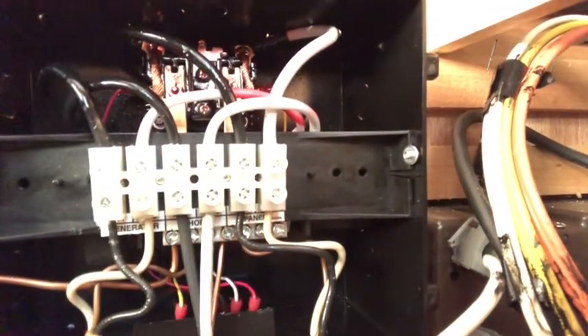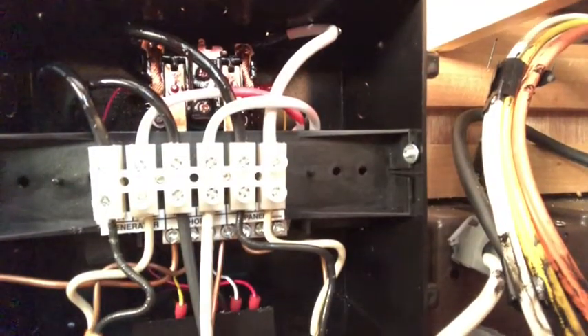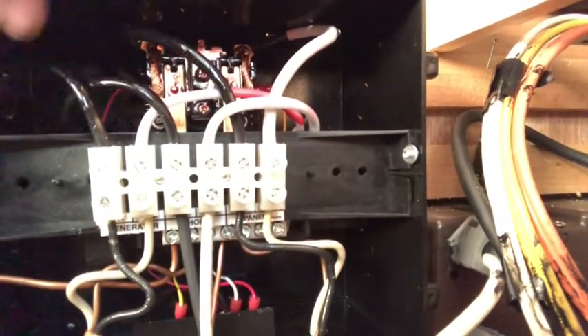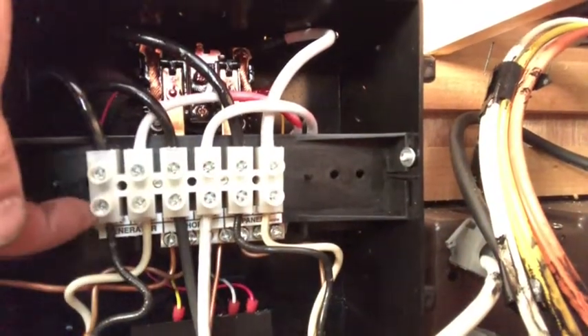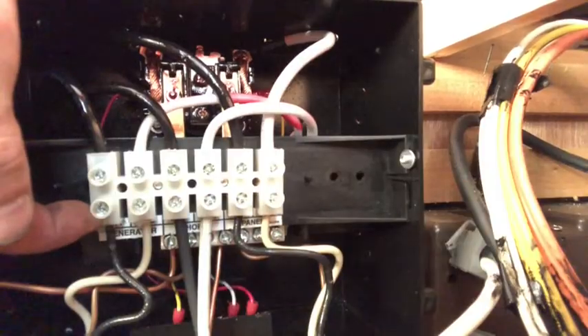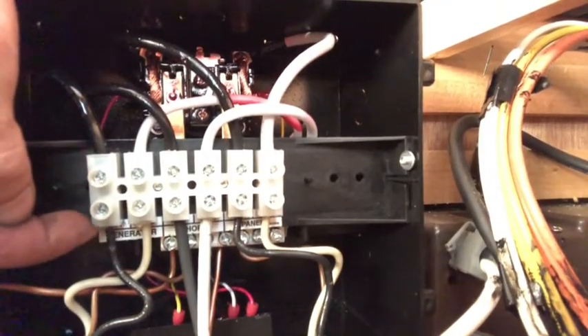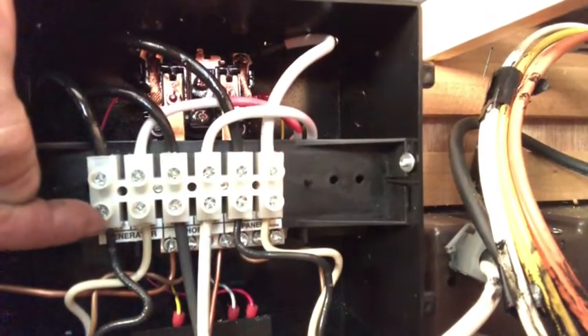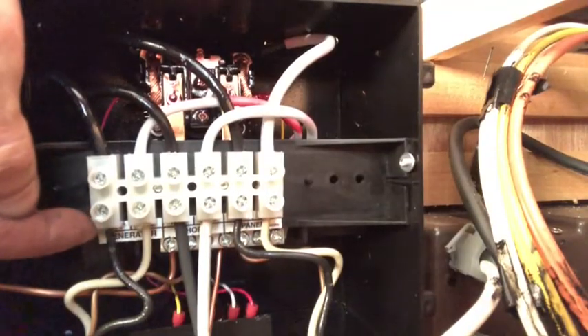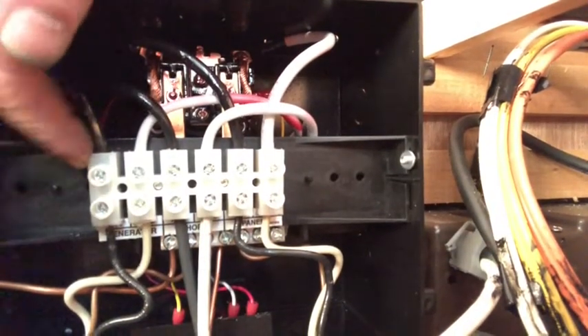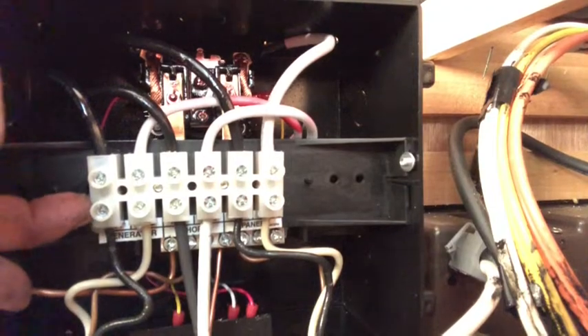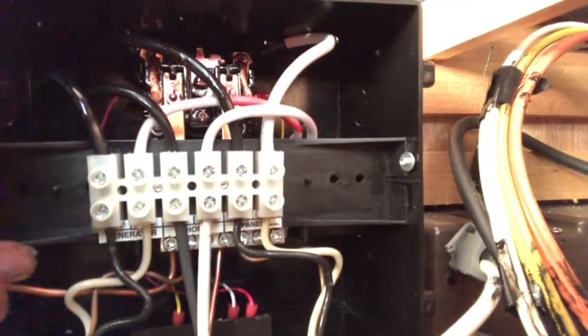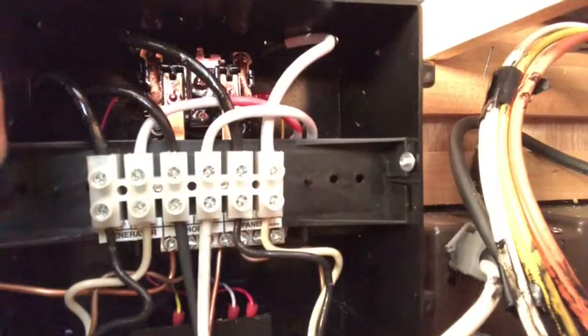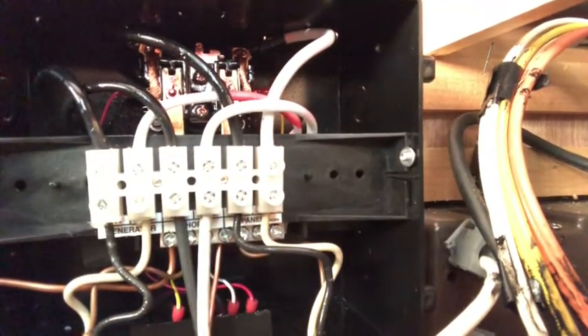And those are the bare wires, or they may be green. You want to make sure that the insulation - the black, white, or green coating - does not go inside the terminal into the clamping area, but does come behind what's white in this case, usually, sometimes black or another color, this plastic. So the insulation should extend into there, but not into the clamping mechanism, or you're not making an electrical connection. Usually it's about 3/4 of an inch that you need to strip.